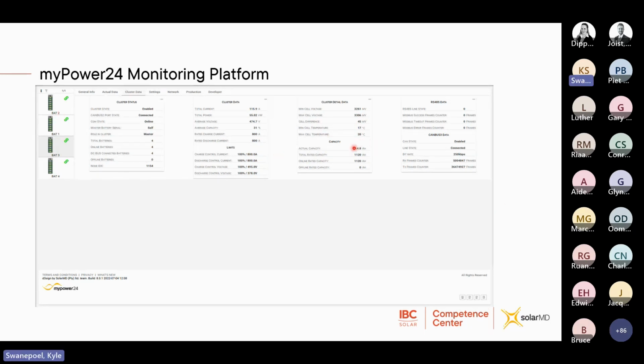This is the usable capacity. So this will be related to the state of charge as well. And this is the total capacity of all of these batteries put together. So it's 280 amp hours across each battery multiplied by 4 will give you your total rated capacity. And because all of the batteries are online, our online rated capacity is 1120. If we had an offline battery, it would show here what that rated capacity is.